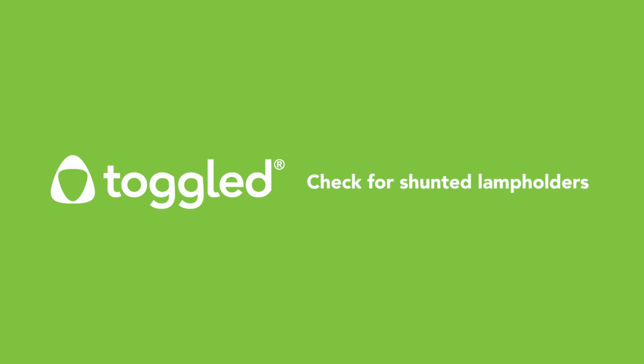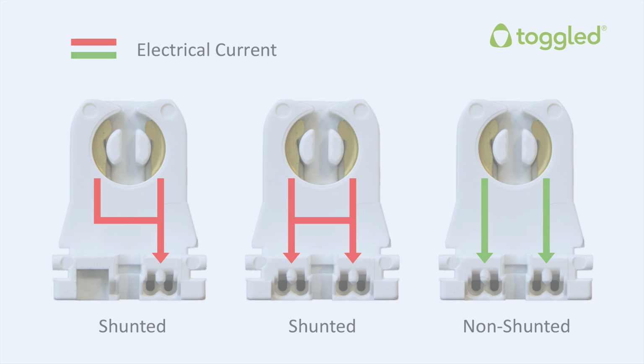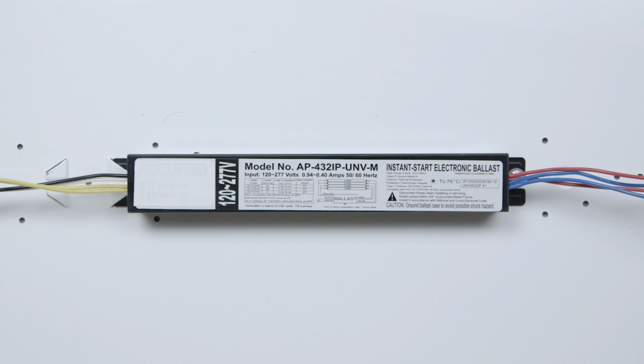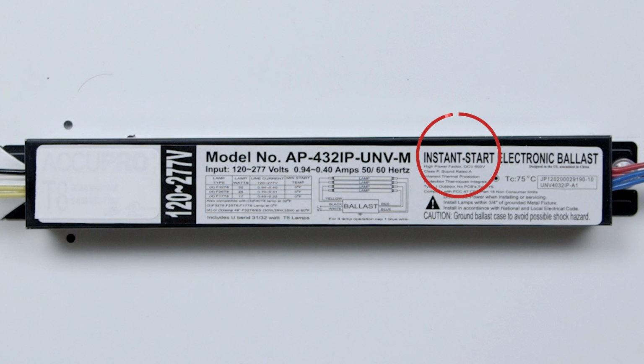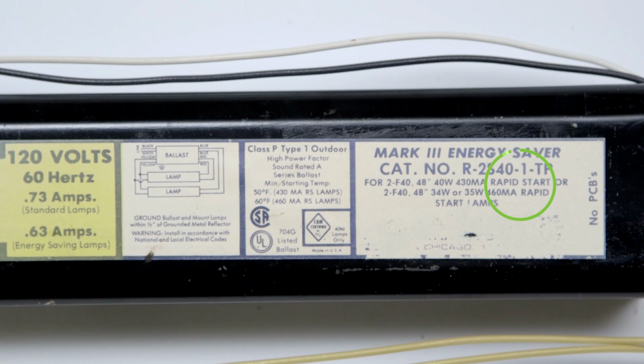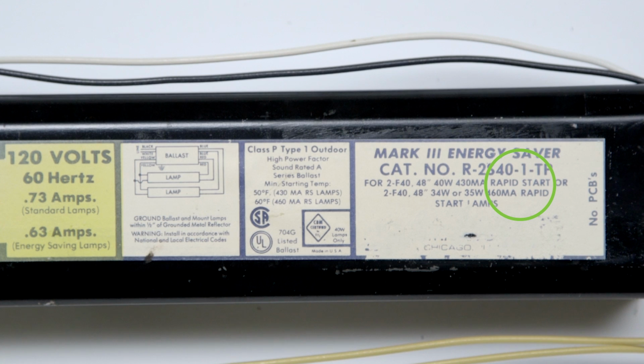Next, check for shunted lamp holders. If present, they will need to be removed and replaced. In a shunted lamp holder, the contacts for the end pins of the lamp are shorted or connected together. Shunted lamp holders are only found in fluorescent systems containing instant start ballasts. Instant start ballasts can be identified by the indication Instant Start, or IS, on the ballast. Rapid start and programmed rapid start ballasts use non-shunted lamp holders that may be reused.